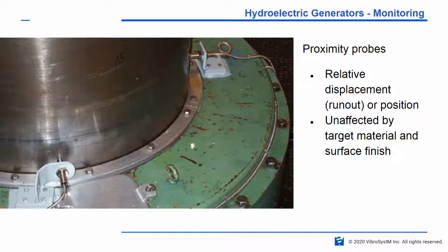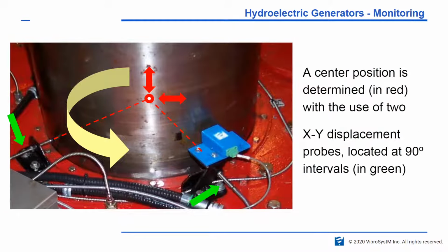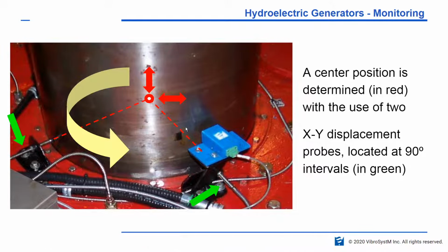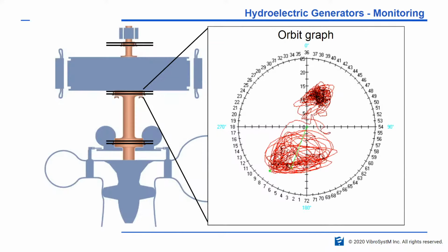Okay, so we have a picture here. Of course, sensors are installed at 90 degree intervals so that you're able to correlate the movement of the shaft in two directions. And that's very useful when you want to produce orbit graphs. The orbit graphs are produced based on the information from two sensors, and you can still see the key phasor here, and the two probes here at 90-degree intervals, monitoring the movement of the shaft as the shaft rotates. And with this information, it's able to produce this type of graph, which all the mechanical engineers understand, and that's basically the position of the shaft while it's rotating.